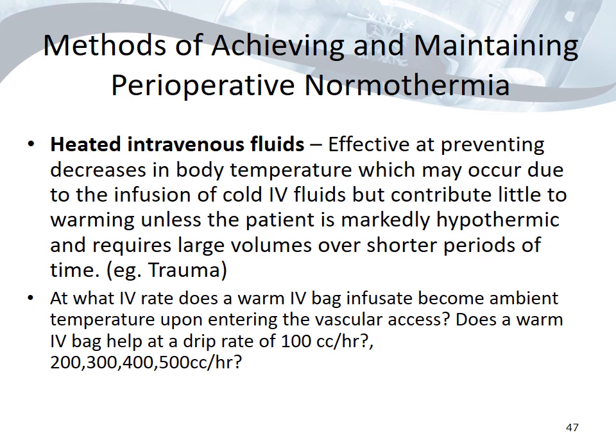What she basically found was if you ran at 1 liter an hour, there was certainly a big difference between the theoretical going into the patient temperature and ambient. A big difference. I think it dropped from 41 degrees to maybe somewhere around 32, something like that, at 1 liter per hour.